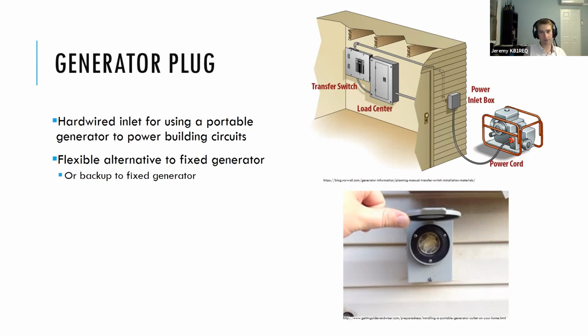And so it allows you to have the functionality of that fixed generator, but you still have the portable generator that you can bring somewhere else if you don't need backup power at that location at the moment. This is also a way to back up a fixed generator. I've seen that in some critical locations where they'll have a fixed generator that'll be ready to go, automatic switchover, but they understand that that is not 100% foolproof, so they have a gen plug as well, so that a temporary portable generator can be brought in in case you have a malfunction with your fixed generator.